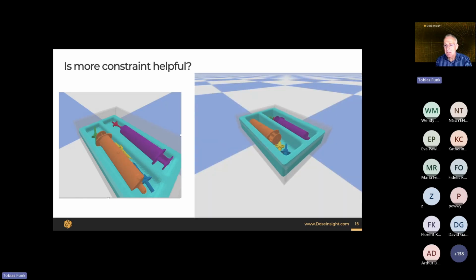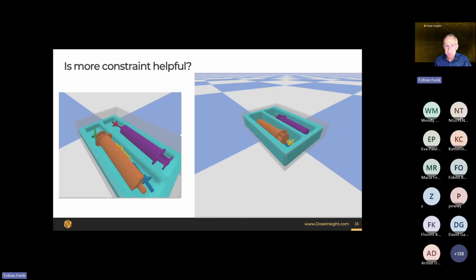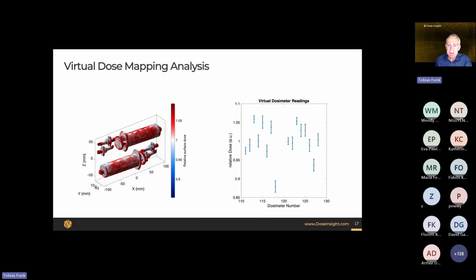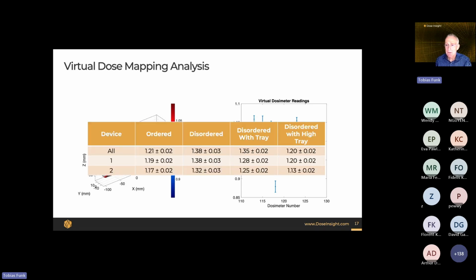What we do about it is we build a packaging that basically prevents the jumping over the fence, but we also reorient the syringes such that now the adapters are trapped behind the plunger here. And just visually we see that there's a lot less variation now. And we can again do our dose mapping, on the left the surface dose, on the right the virtual dosimeter readings, and we can calculate our dose uniformity ratio, and we see that it went down significantly to 1.2. But that's as good as the actual ordered case. So that's great. But let's go a little bit further.